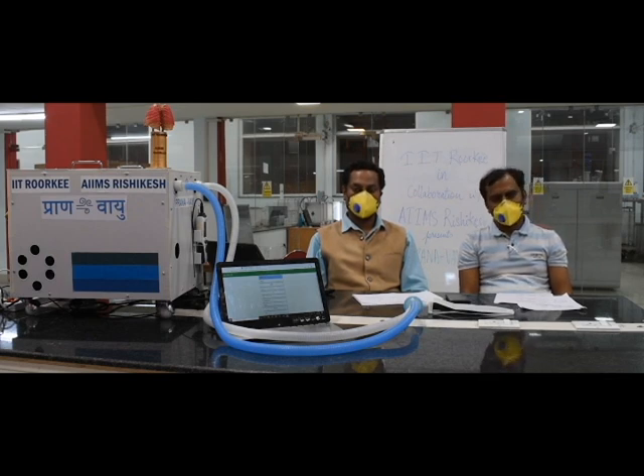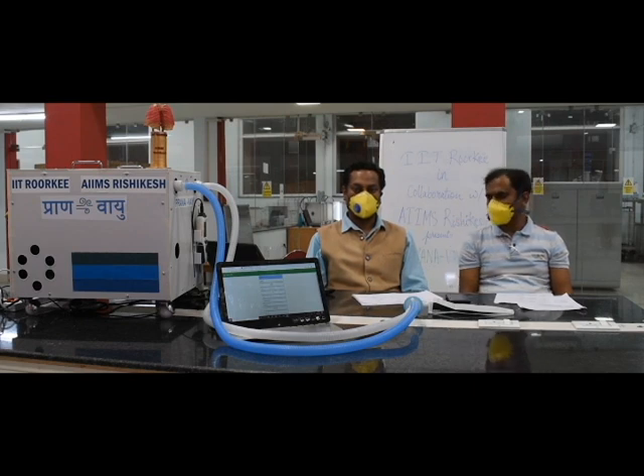Let's take the settings once again similar, that means 400 cc of tidal volume with a respiratory rate of 15, inspiration to expiration time ratio let us take as 1:2, and here as the triggering is involved, during triggering the lung pressure will be going in the downward direction. So let's take the lung pressure as -2 cm of H2O. That means the ventilator will trigger its operation whenever the lung pressure falls below atmosphere up to 2 cm of water column, right? So let me set my ventilator in that mode, then I'll show you the graph.